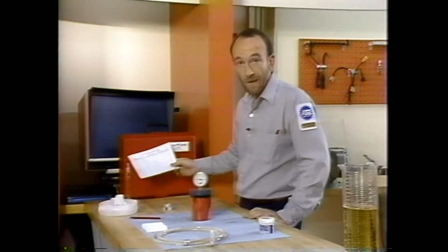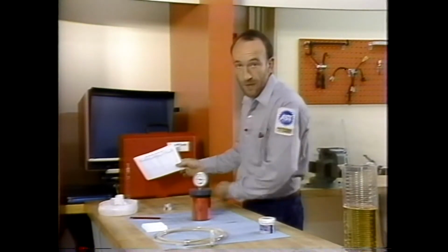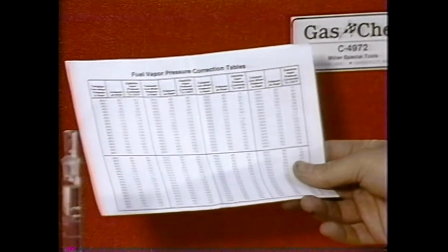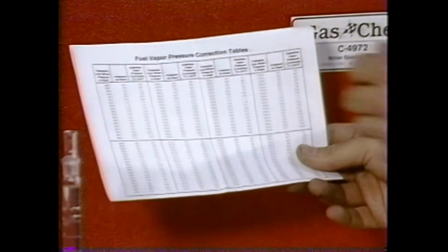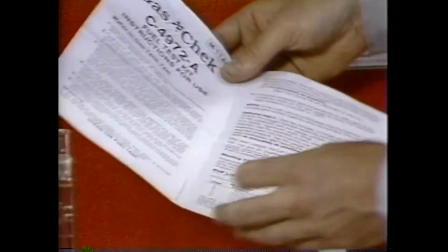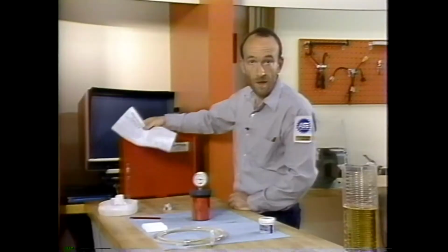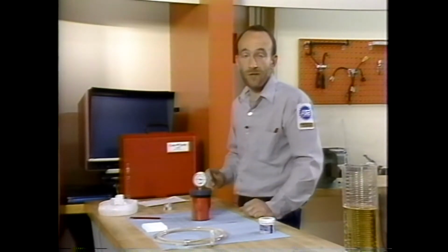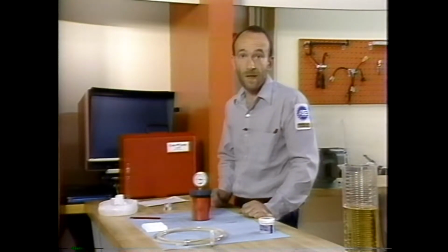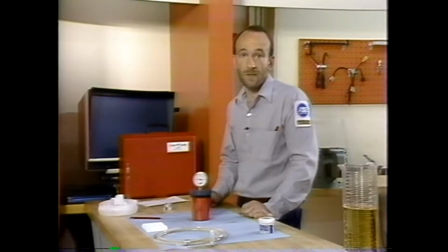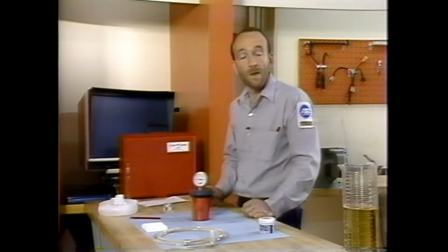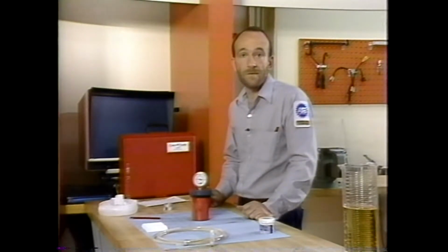Now, once we've obtained our vapor pressure from this chart in the instructions, we'll want to compare that with what the vapor pressure limit should be. There's a second chart in the back of the instructions here which gives us those limits. If we have fuel that has vapor pressure that's higher than what those limits should be, this could cause problems such as hot starting or vapor lock. And that completes the gas check procedure.